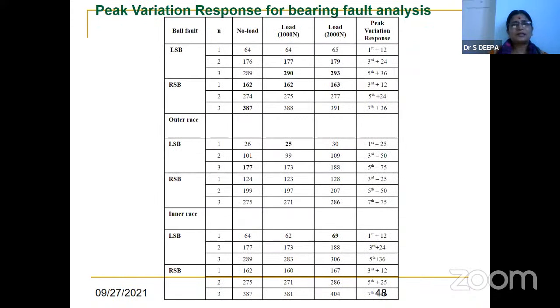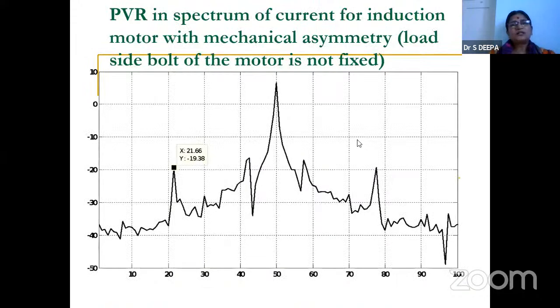And this is the overall table for the bearing. There was some pattern occurring during the bearing fault for different faults. Here, this one is from when I was doing the experiment in the shed. I forgot to fix the bolt on one side of the machine, so the machine started vibrating, and at that time I took the readings.